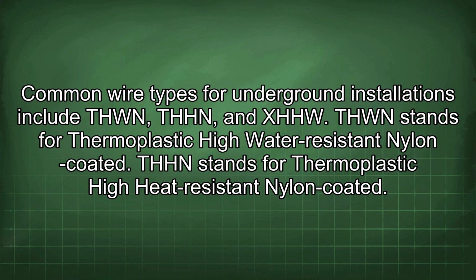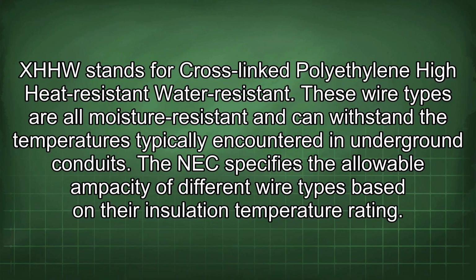THWN stands for thermoplastic high water resistant nylon coated. THHN stands for thermoplastic high heat resistant nylon coated. XHHW stands for cross-linked polyethylene high heat resistant water resistant. These wire types are all moisture resistant and can withstand the temperatures typically encountered in underground conduits.